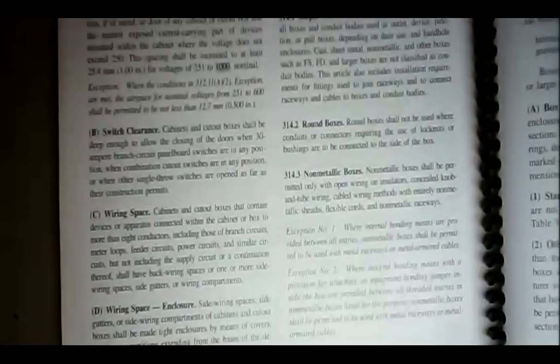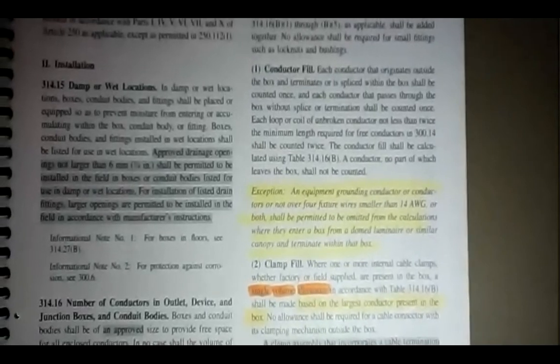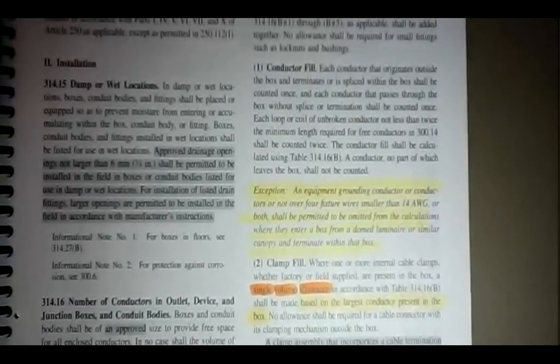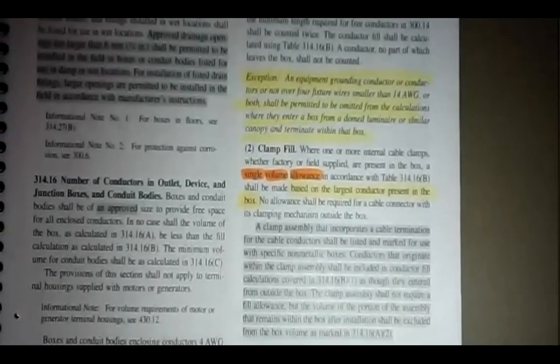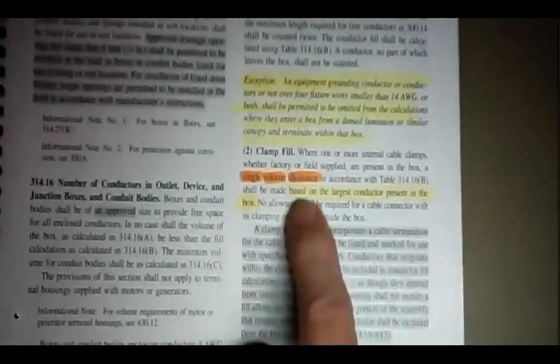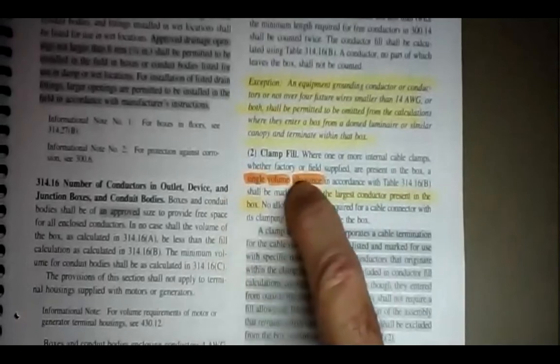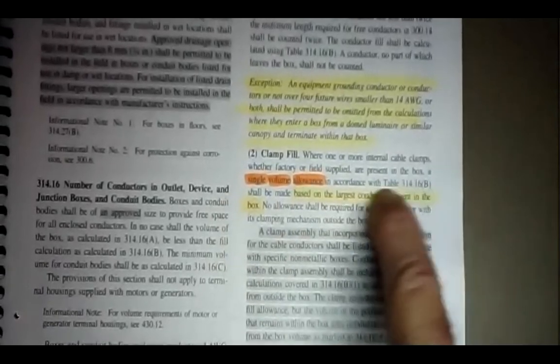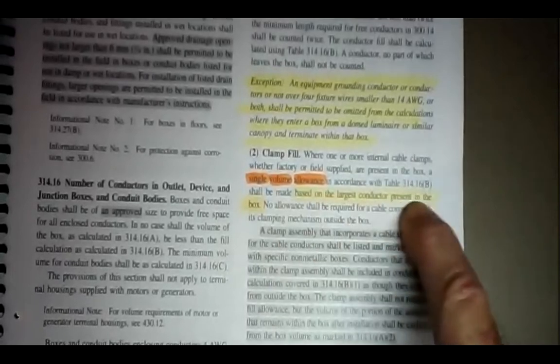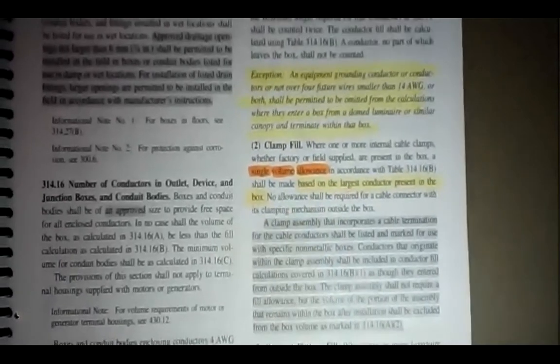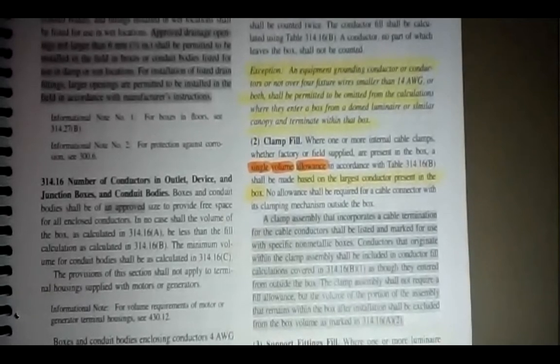So that's how you use these two tables. If you have a fixture stud or fixture hickey you deduct one wire. Actually, I didn't cover cable clamps yet — clamp fill: where one or more internal cable clamps are present in a box, a single volume allowance per table 314.16B shall be made based on the largest conductor present.